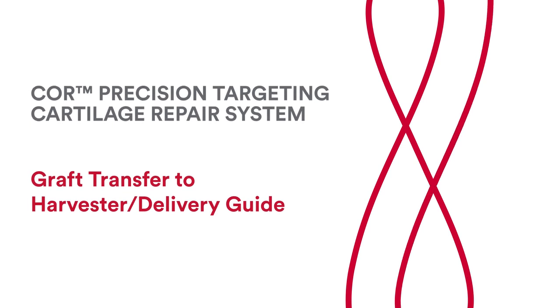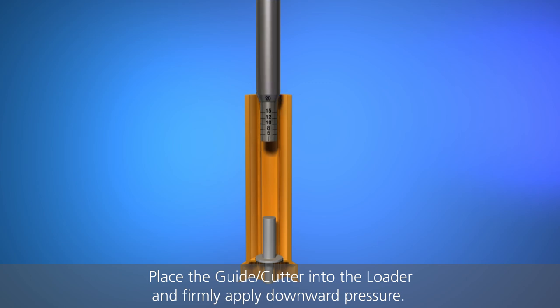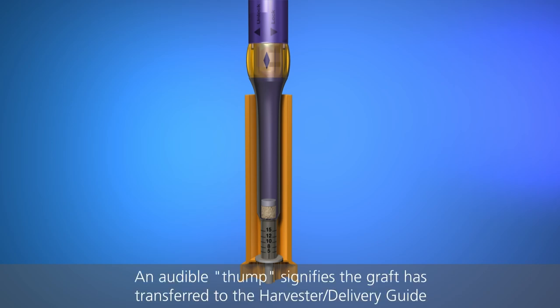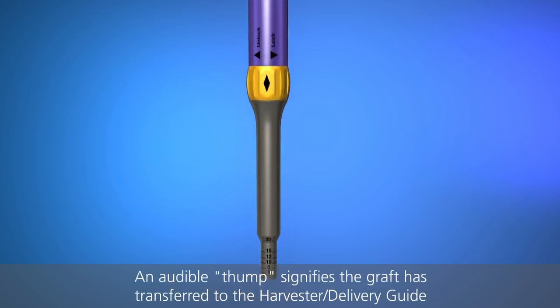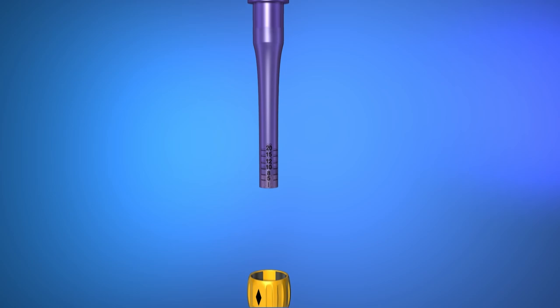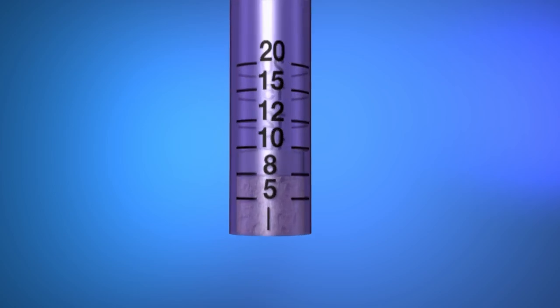Graft transfer to harvester delivery guide. On a firm surface, insert the guide cutter into the graft loader. Firmly push the guide cutter until it makes contact with the bottom of the loader. Remove the cutter from the guide by twisting the bayonet ring to the unlock position. Inspect graft. Keep it within the delivery guide until transplant.